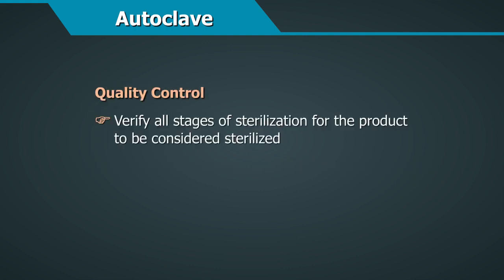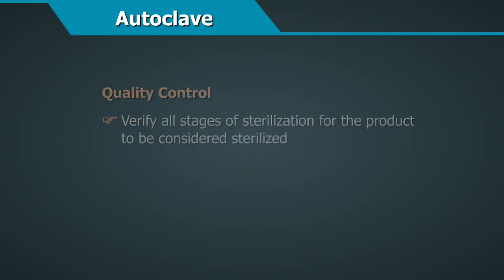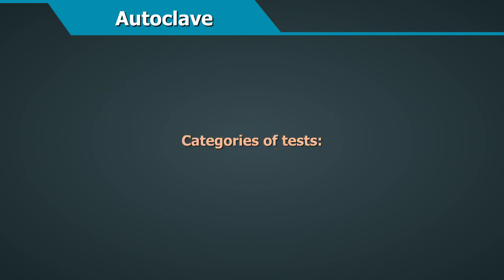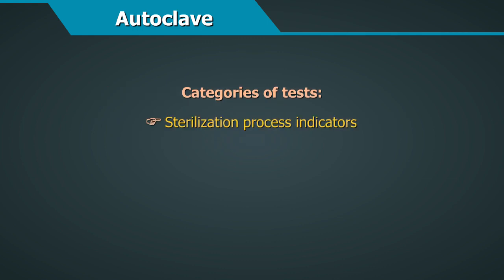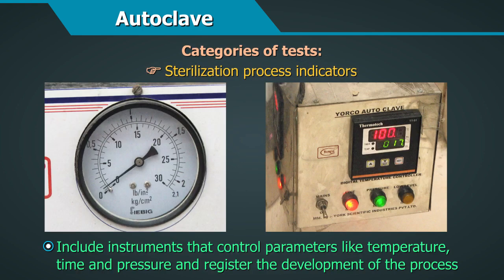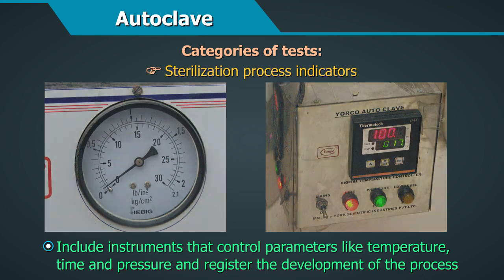Quality control. In order for a product to be considered sterilized, it is necessary to verify that all the stages of the sterilization process have been carried out correctly. Different categories of tests are sterilization process indicators. These are designed for supervising the functioning of the autoclaves. They include instruments that control parameters like temperature, time, and pressure and register the development of the process.